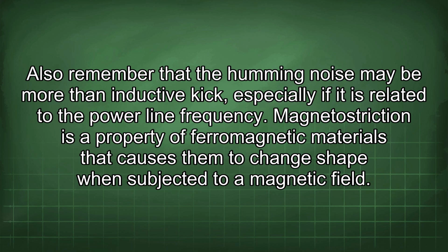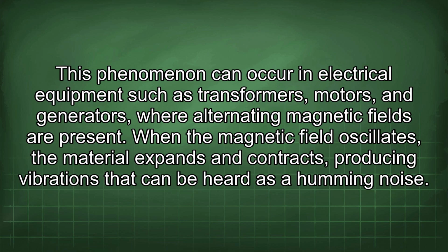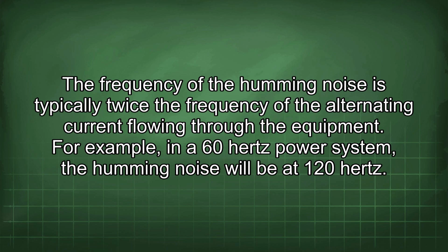Also remember that the humming noise may be more than inductive kick, especially if it is related to the power line frequency. Magnetostriction is a property of ferromagnetic materials that causes them to change shape when subjected to a magnetic field. This phenomenon can occur in electrical equipment such as transformers, motors, and generators, where alternating magnetic fields are present.